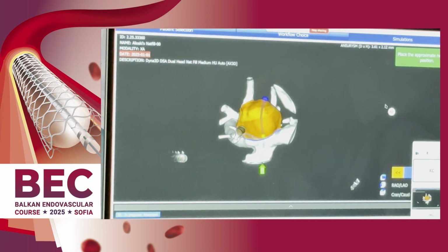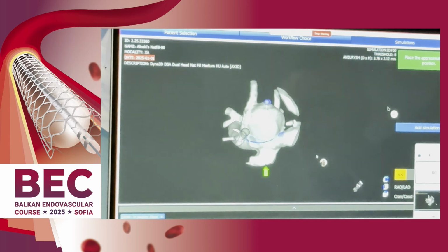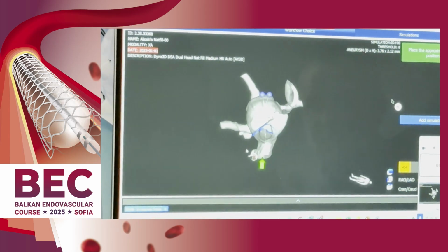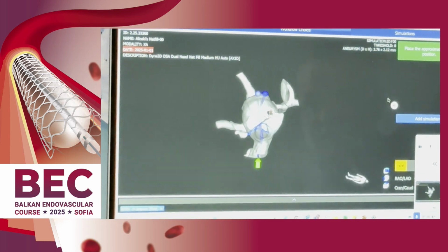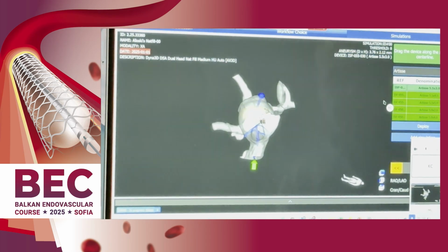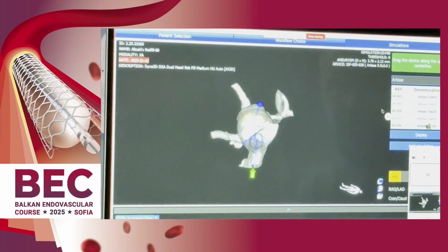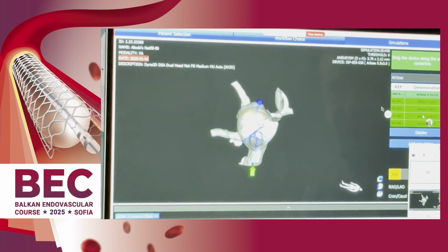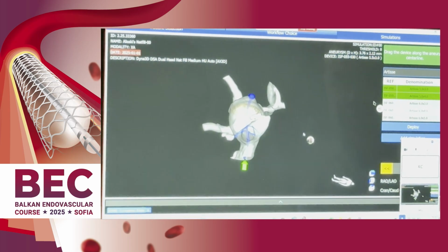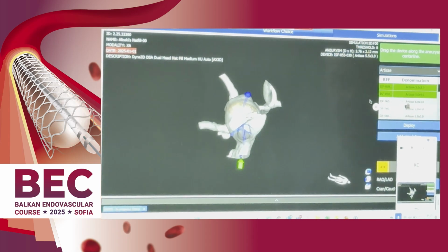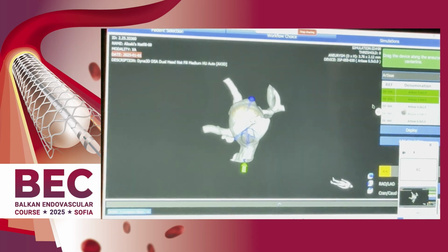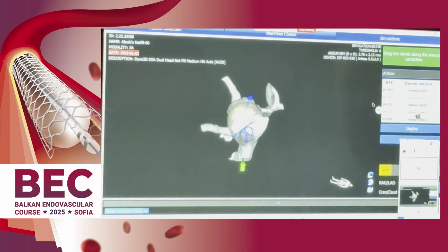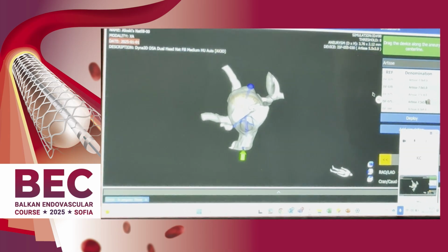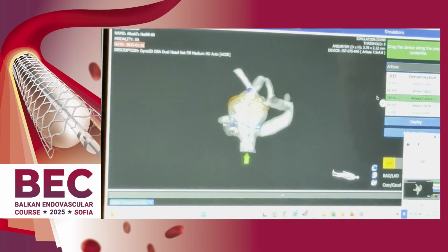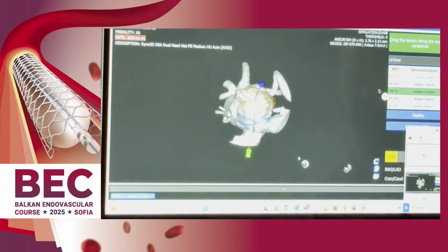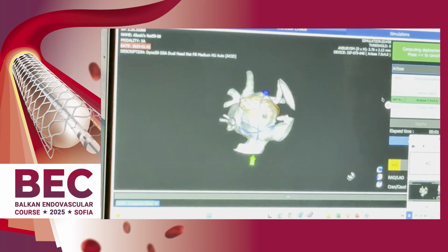Sizing the device. To ensure proper selection, measure the aneurysm in the anterior, posterior, and lateral planes. The sizing chart provides recommendations based on aneurysm dimensions, accounting for slight oversizing. The final size may vary depending on aneurysm shape. Sizing example: for accurate device selection, measure aneurysm width, height, and neck size in 2 projections. If the aneurysm width is between recommended sizes, a larger device may be selected while considering aneurysm height. For example, an aneurysm with an average width of 4.8 mm and height of 7.5 mm would require an Artisse 6.5 by 5.0 implant.